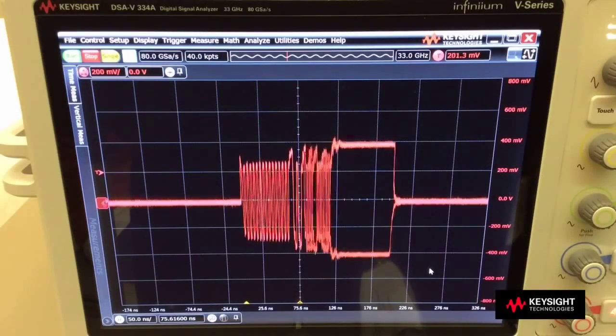The third customer need that the V-Series addresses is to provide the InfiniiMode feature, which is the ability to make differential, single-ended and common mode measurements using one probe tip without reconnecting the signal. So the InfiniiMax III probing solution will provide the InfiniiMode capability up to 20 GHz of bandwidth.